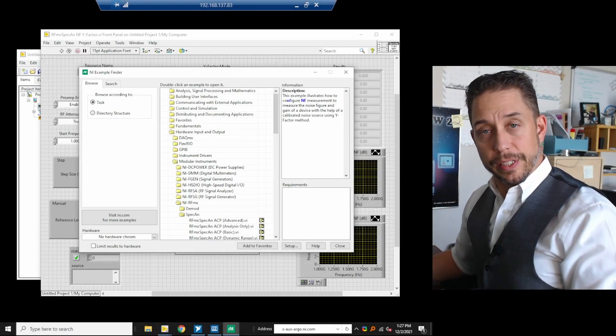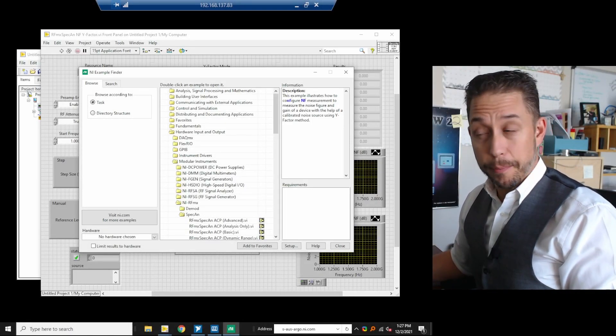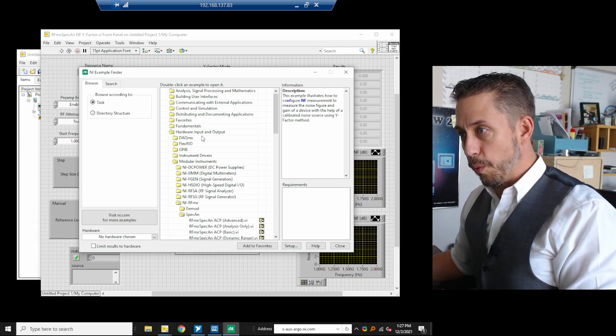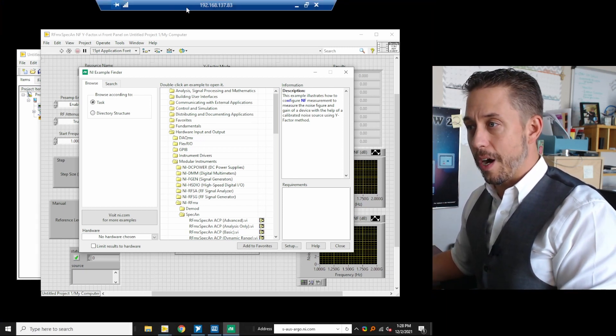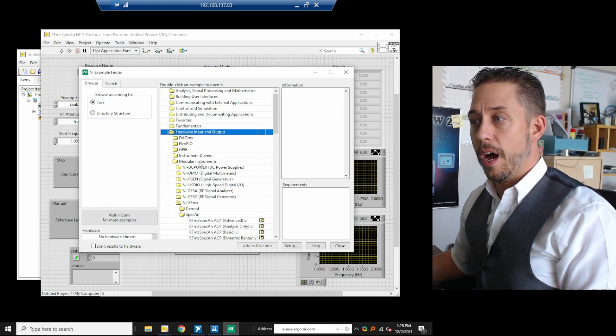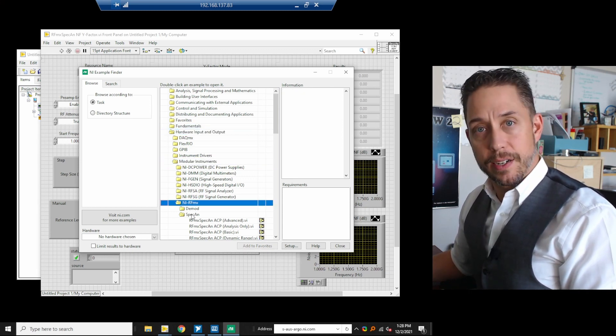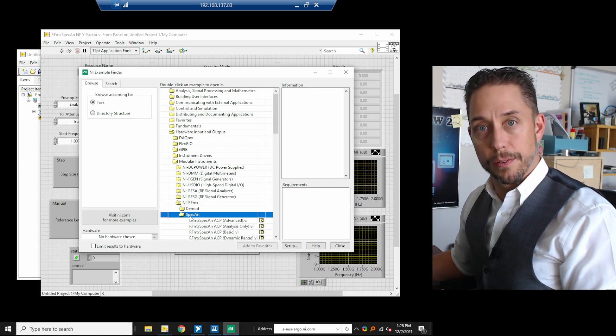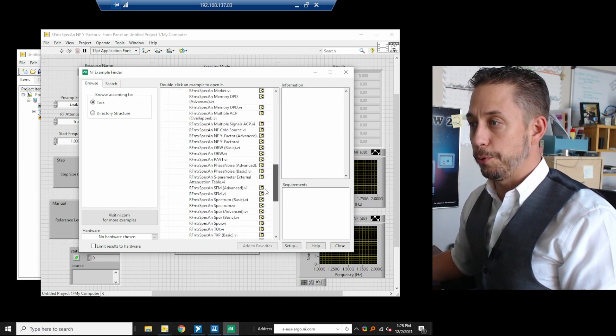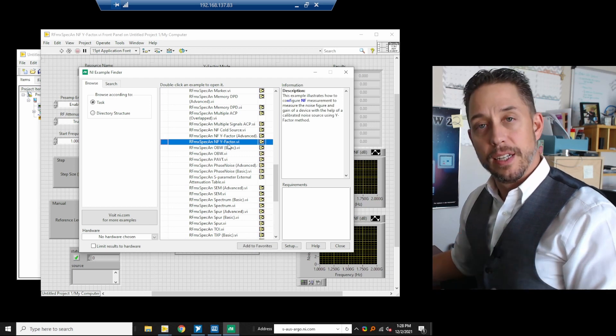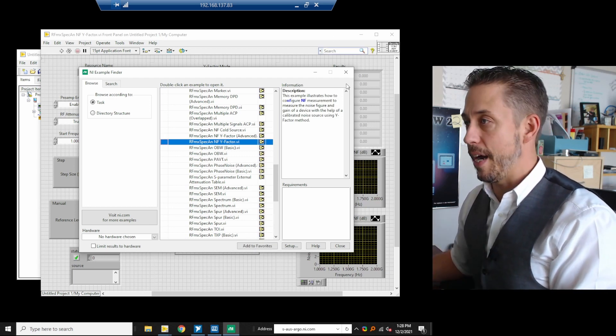Now let's look at how to do this same calibration and measurement from the API itself. In LabVIEW, we use the Example Finder. Navigate to Hardware I/O → Modular Instruments → RFMX → SpecAn, then scroll down to find the SpecAn NF Y-Factor example — that's the example we have open.